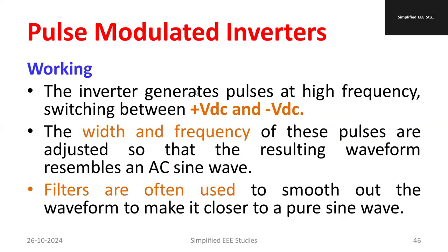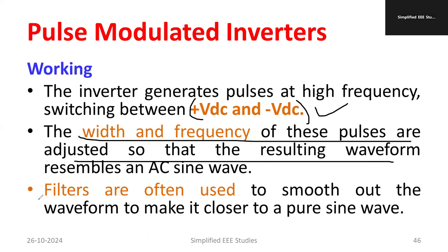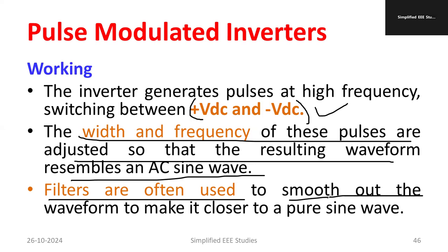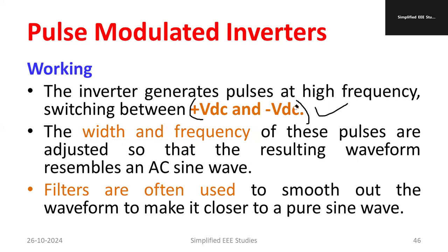The inverter generates pulses at high frequency. The switching frequency is very high, lying between +VDC and −VDC. The width and frequency of these pulses are adjusted so that the resulting waveform is similar to an AC sine wave, with on and off periods adjusted to obtain an output voltage similar to a sinusoidal waveform. Filters are commonly used to remove noise and unwanted signals, making the waveform much closer to a pure sine wave, so the harmonic content is comparatively less.